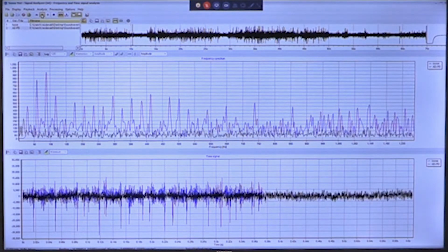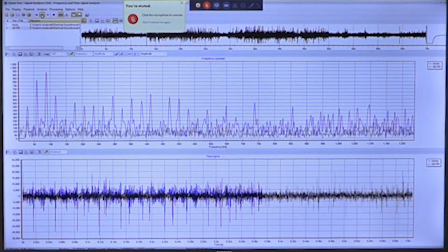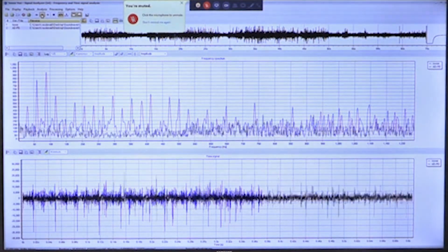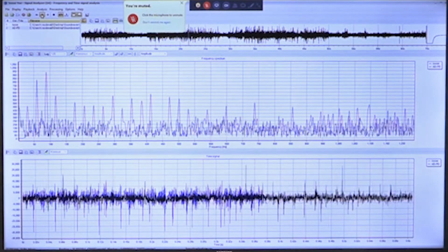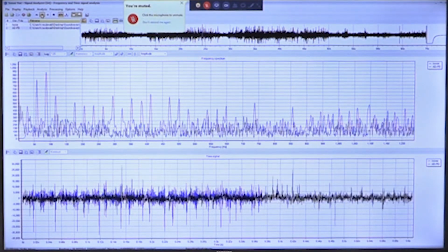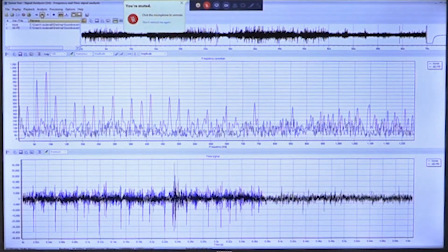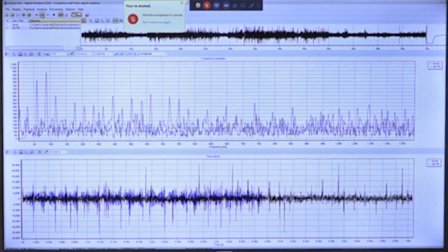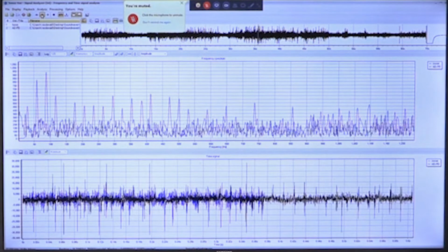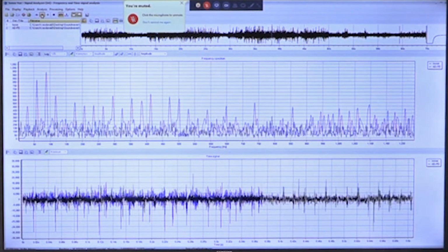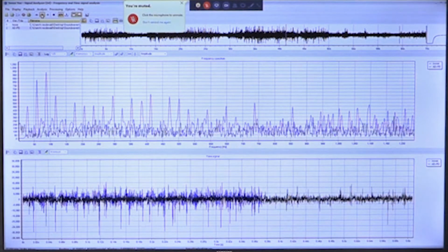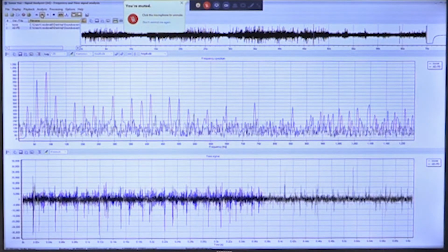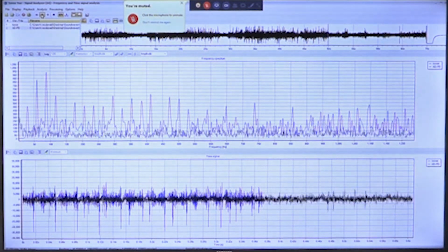So now originally when I recorded this sound wave, it was kind of an unknown electrical event. After I came on board with Iris, we have another device that does transient earth voltage testing, and I learned from that company that, hey, this is actually a partial discharge event that we're picking up. Oh, wow. So all these years that people have heard this little sound, but it wasn't really giving any good harmonic indications, it's actually a partial discharge event. So maybe a very small nick in the wiring when somebody's pulling the cable through. Maybe there were oxidized holes in the curing process of the wire's insulation. So it's kind of cool to go from not knowing initially to suddenly now, hey, this is a known event and this is a partial discharge.